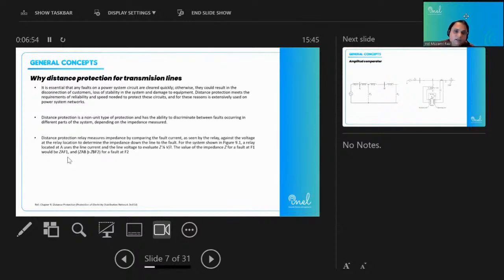We have to avoid the unnecessary outages which may be caused. One reason may be the fault, and the other reason is the mal-operation of the equipment connected. So we need to keep an eye on the network operation. If it is a fault of a permanent nature, then there should be a disconnection of that transmission line. But if the fault is temporary in nature, then there should be an auto reclosing operation. If the transmission line is out on a temporary fault, then after some time we need to reclose it automatically.